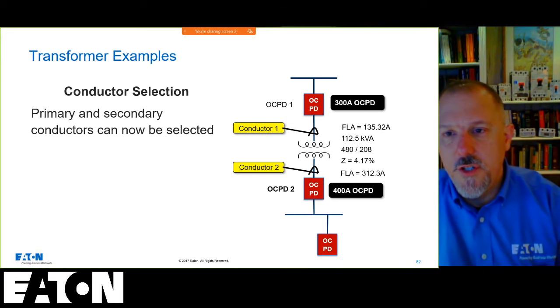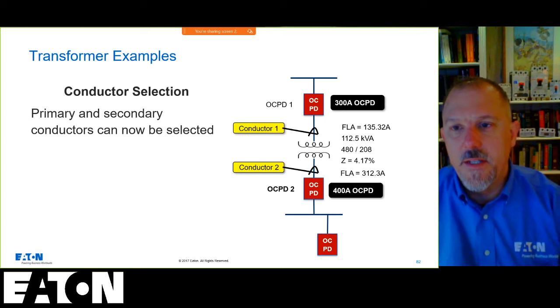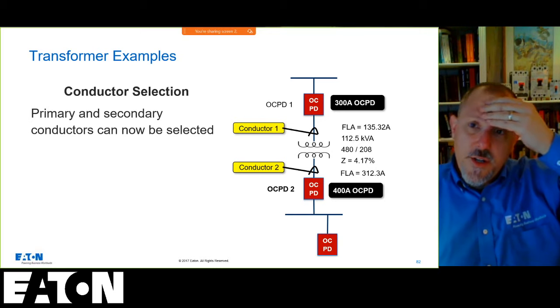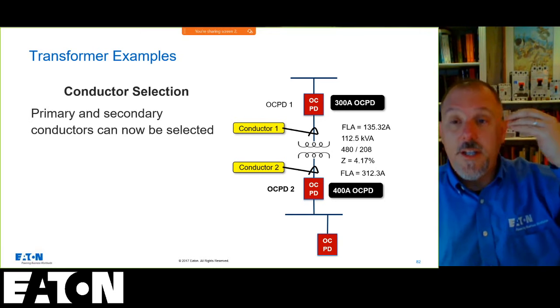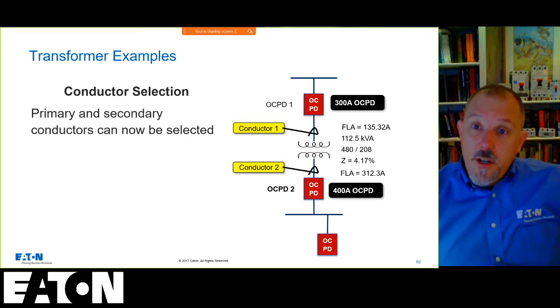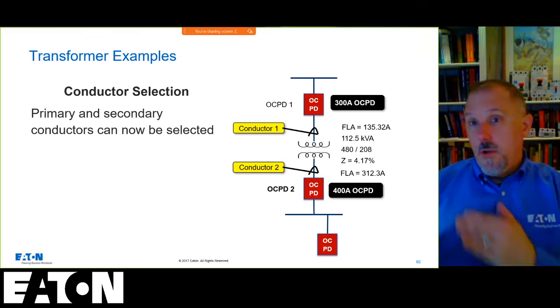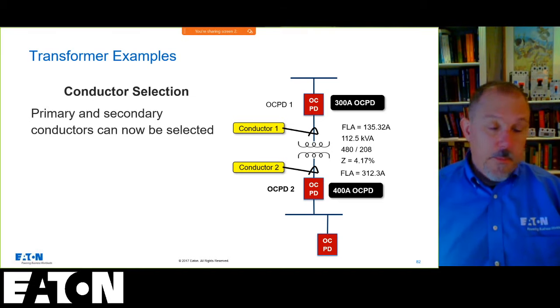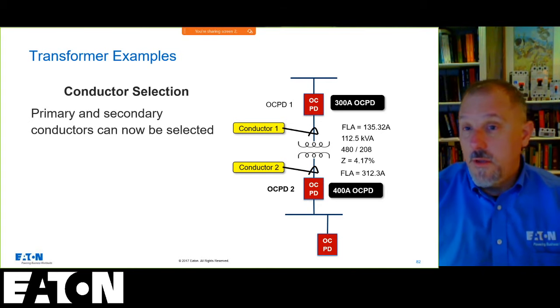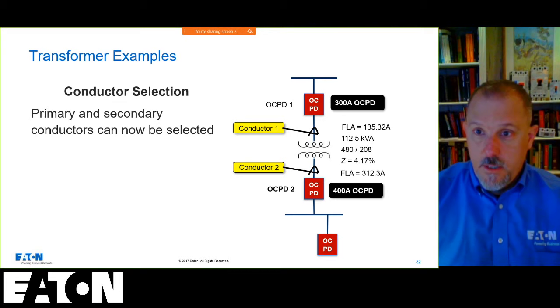Okay, 125 is used to load the transformer at 80%, which is where it has best efficiency typically. Yeah, you want to load that transformer. You don't want to overload it. You don't want to cook it. You want it to work for you, though. And there's a drive that says that we're not loading these transformers up as much as we probably should because of the way we do load calculations. And I've had some people put ammeters on the outsides of the building and show that the transformer is very lightly loaded. Single phase wave from, I'm not going to get into that. All right.